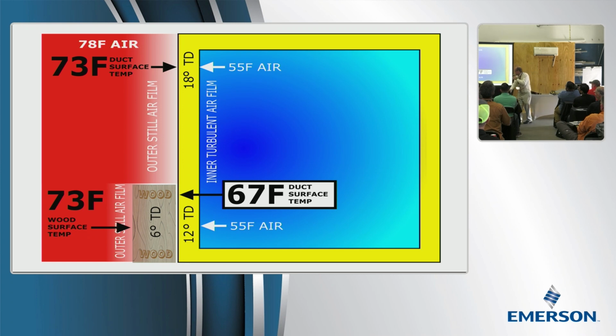And what's going to happen is in between this, you've made a composite. You're conducting, you're touching. You're conducting right through. You've made a 67 degree area on your duct that would have been 73. But because you put it up against a piece of wood, you've composited that wood right into your ductwork. The only way you could make it worse, and you've seen this, is let's paint mastic over them and make them all one. We'll just mastic the whole thing so it's one big clump. And this is really a very common problem.